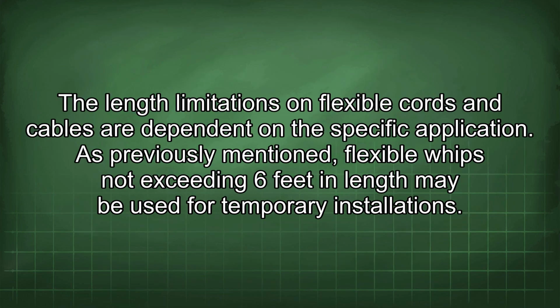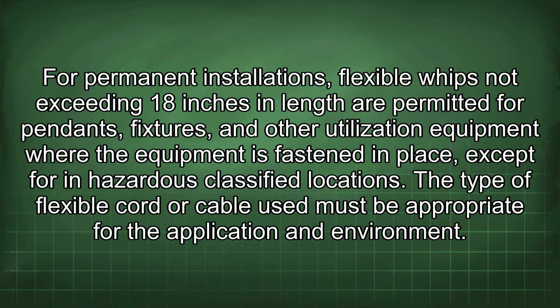The length limitations on flexible cords and cables are dependent on the specific application. As previously mentioned, flexible cords not exceeding 6 feet in length may be used for temporary installations. For permanent installations, flexible cords not exceeding 18 inches in length are permitted for pendants, fixtures, and other utilization equipment where the equipment is fastened in place, except in hazardous classified locations.